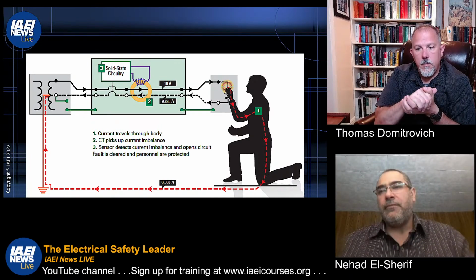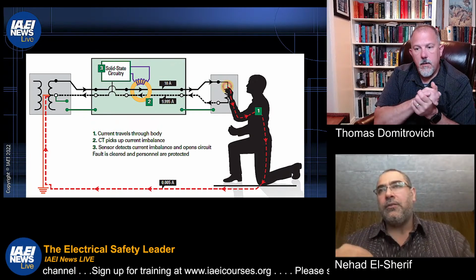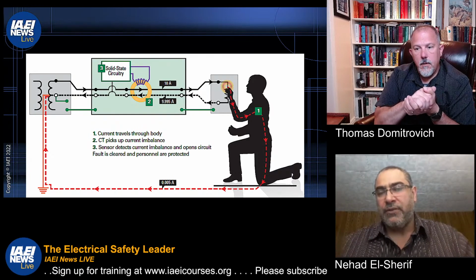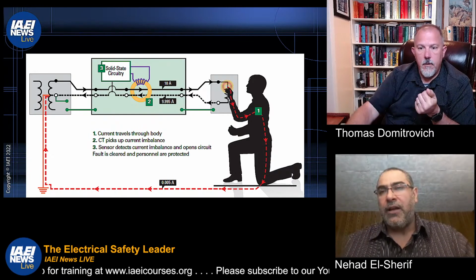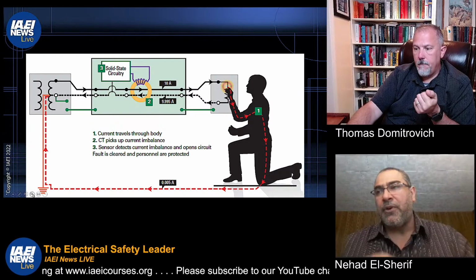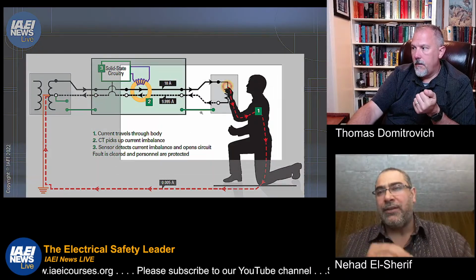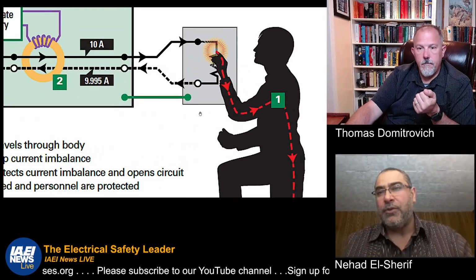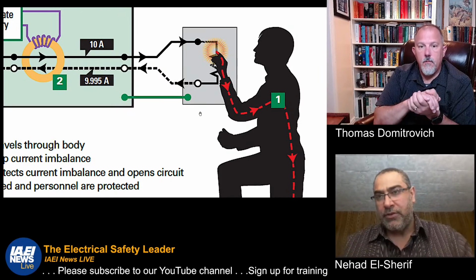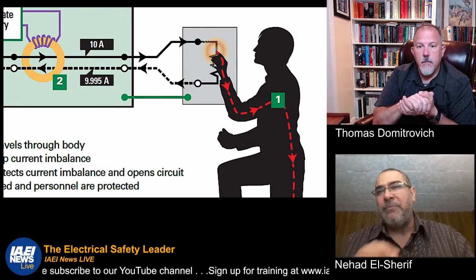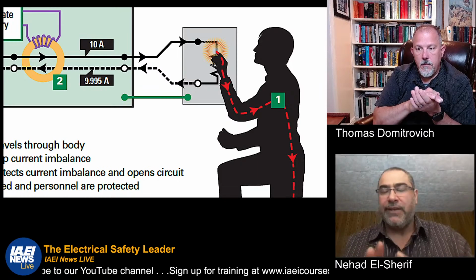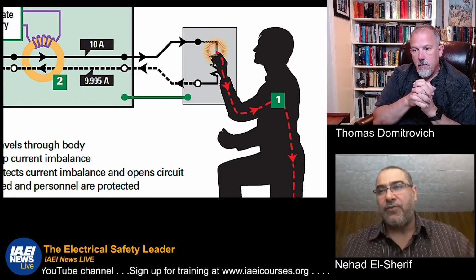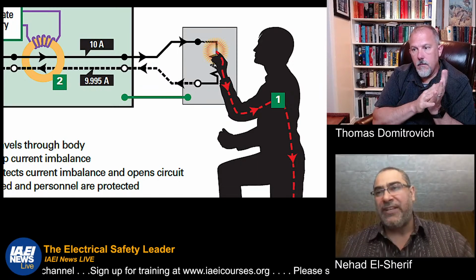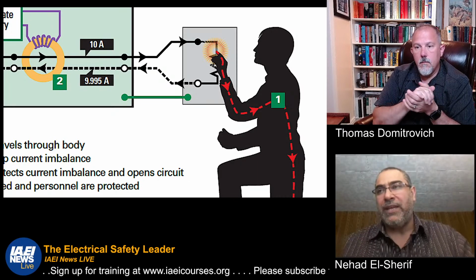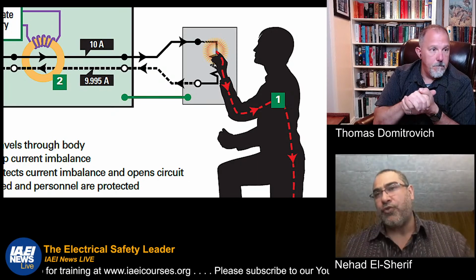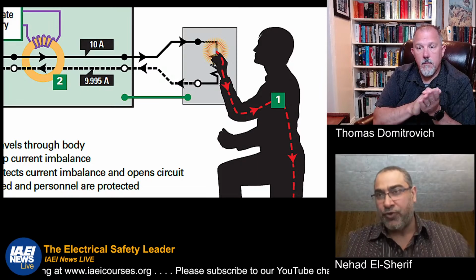The problem arises when, just like Tom is showing on the screen here, we have an alternative path for current. And remember, electrons are smart and they will take every path available to go back to the source that they originated from. It doesn't matter what the impedance is, because it's a common mistake to think that electrons will take the path of least resistance. This is not true. They will take any path, but more electrons would go to the path of least resistance for sure.